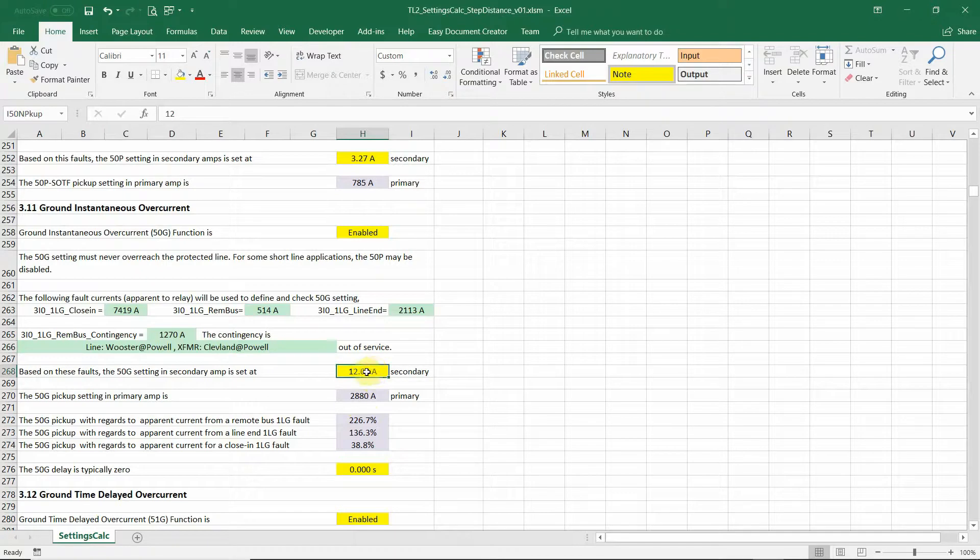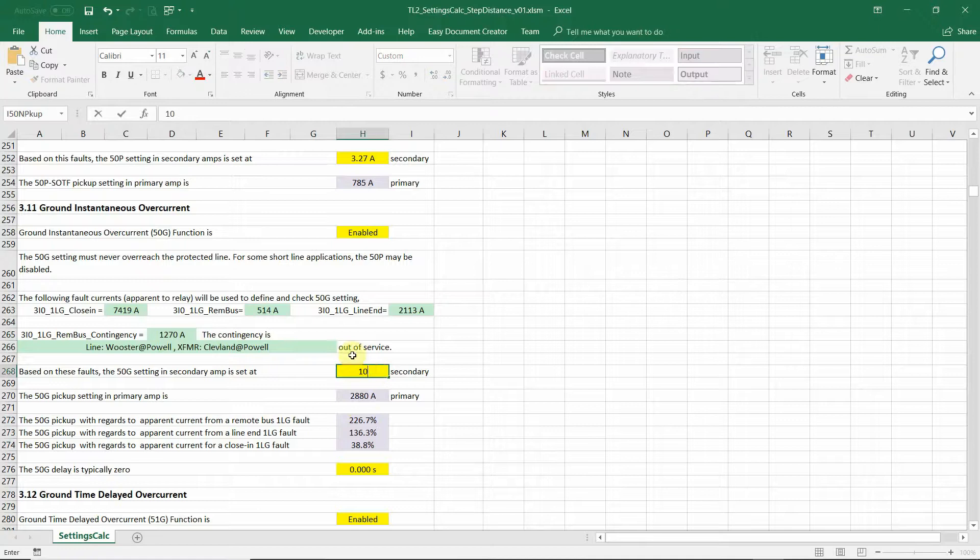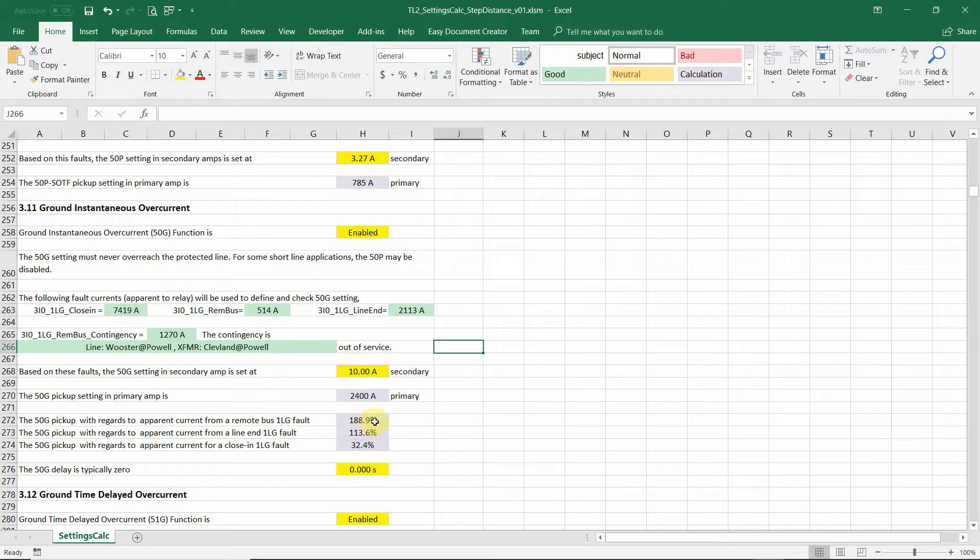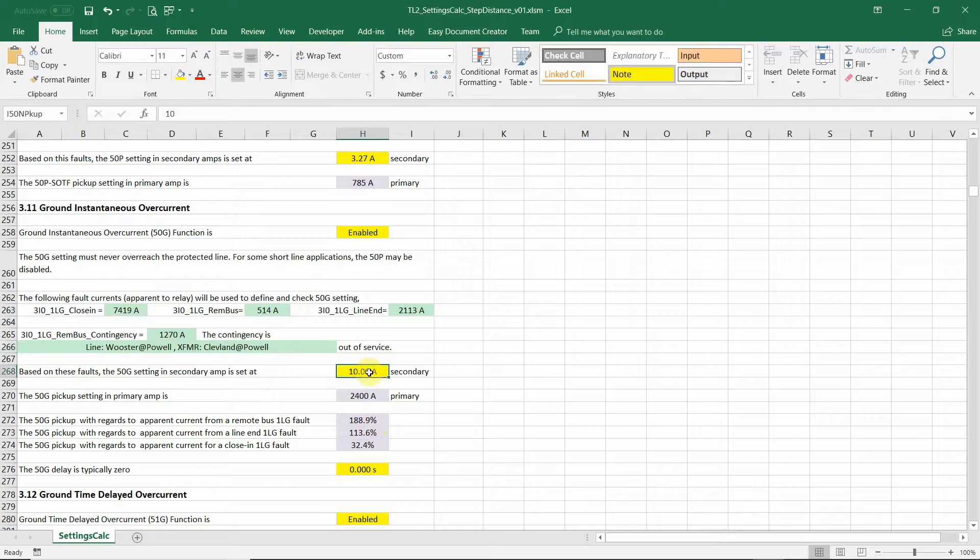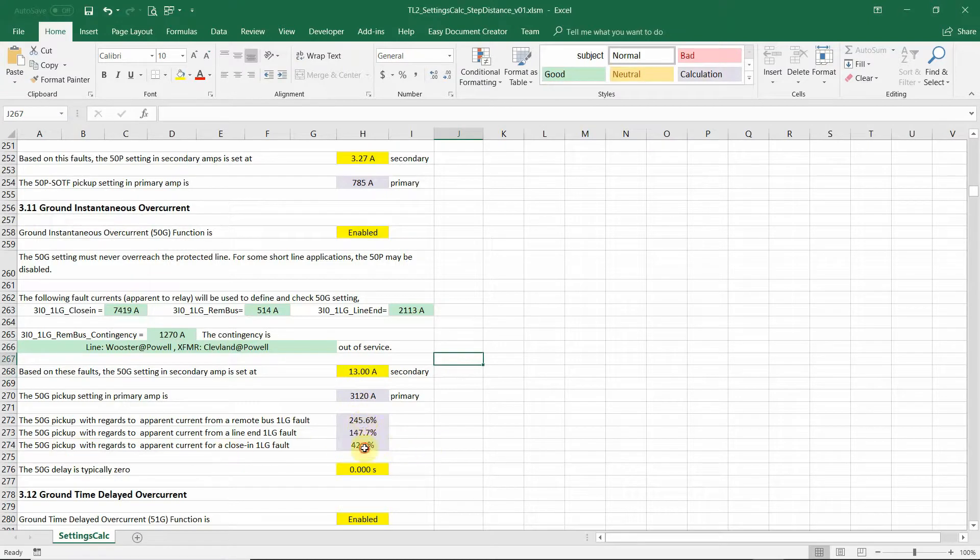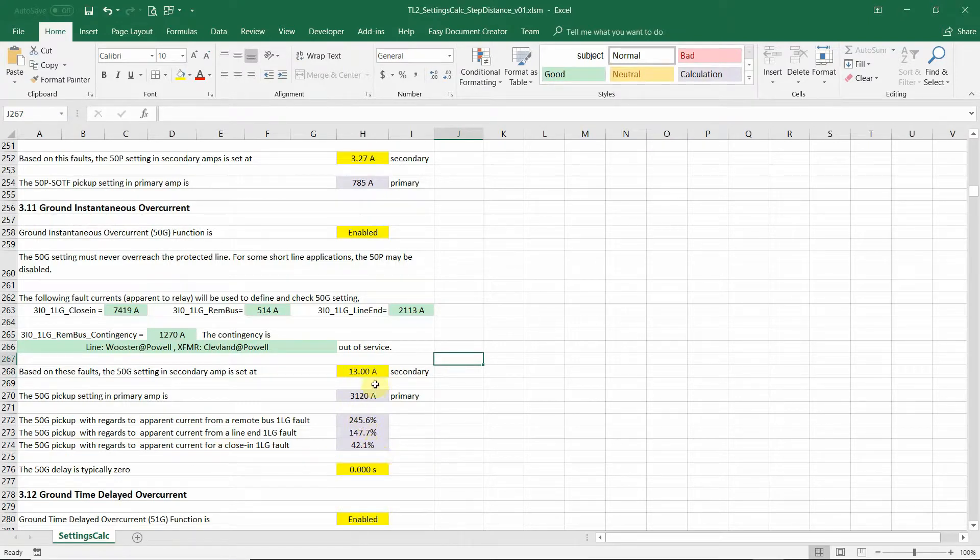If you want this element to be more sensitive, you can change it to say 10 amps. It is still a valid setting, just a less security margin. Or you want to be conservative, you can change it to 13 amps. Give a more margin there.